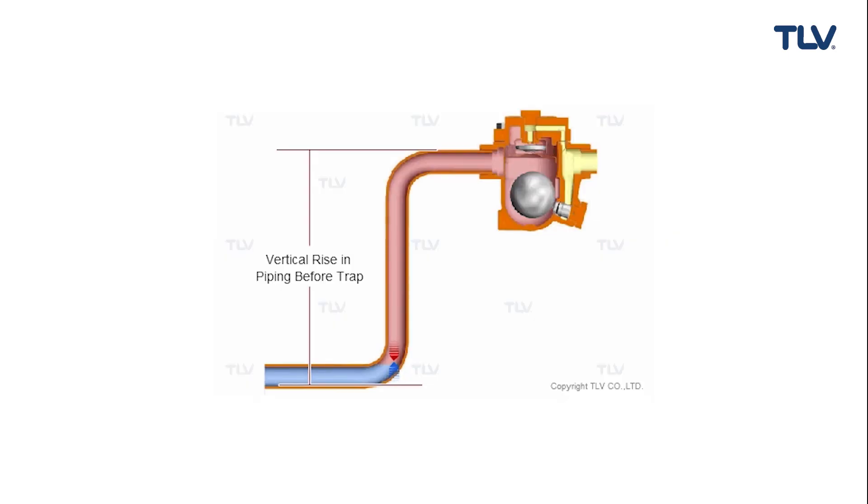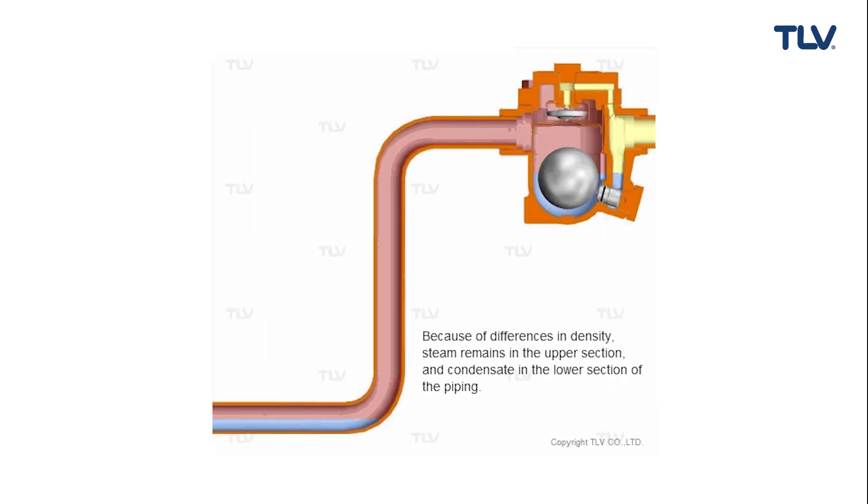Condensate and steam at the inlet side of a trap experience the same inlet pressure, because traps are designed to discharge condensate with minimal steam loss. So steam, which has a lower density than condensate, will logically rise above the condensate when there is a vertical rise and enter the trap before the condensate, causing the valve to shut.